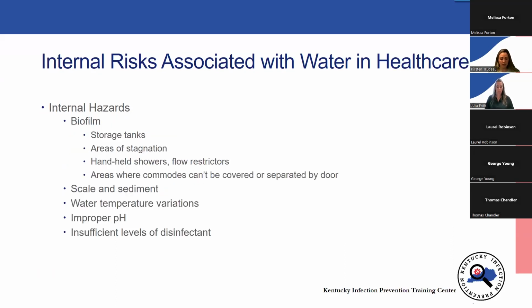Internally, some hazards include anywhere biofilm can form: storage tanks, areas of stagnation, handheld showers, flow restrictors, areas where commodes or toilets can't be covered or separated by a door. Risk also includes any place where scale or sediment can form, variations in water temperature, off pH levels, and insufficient levels of disinfectant.